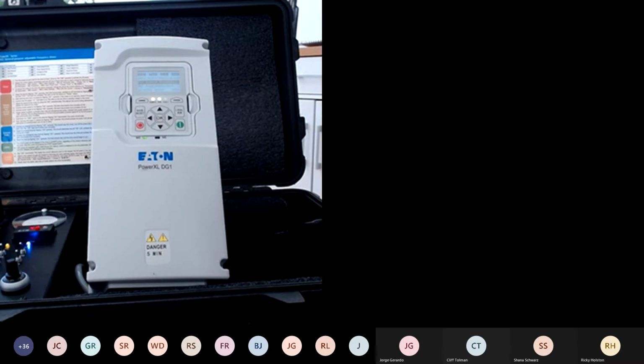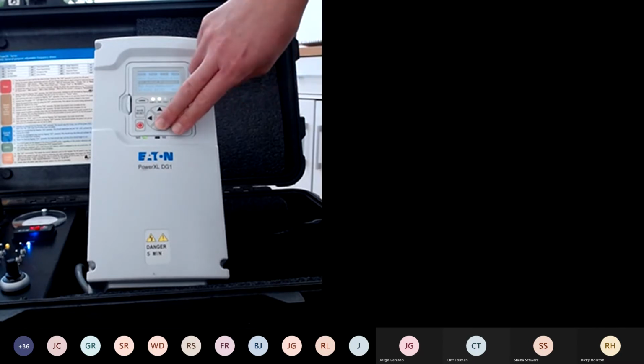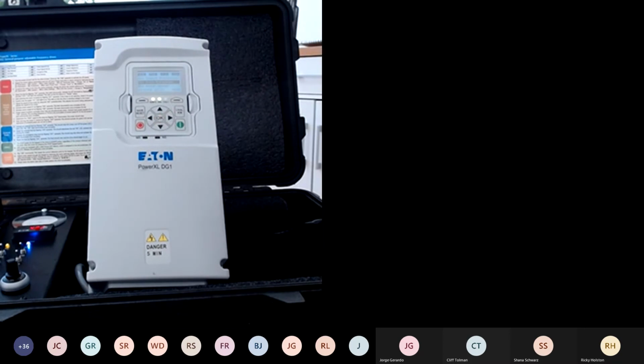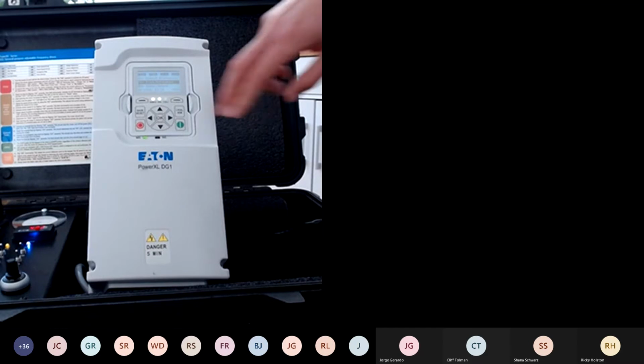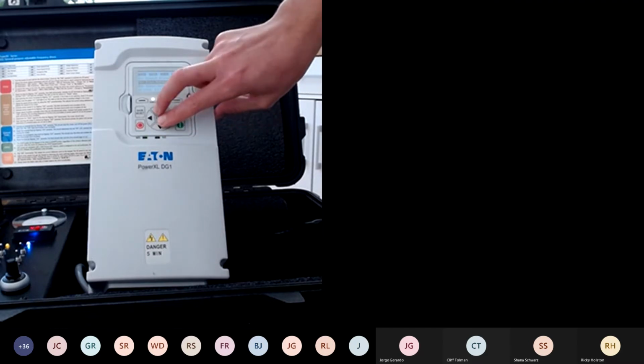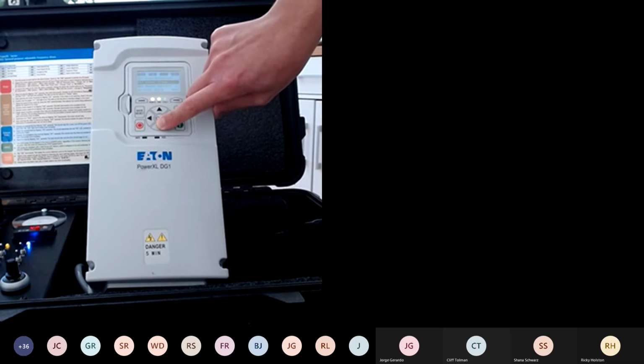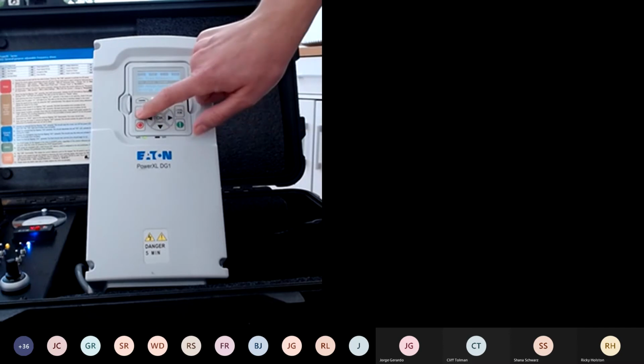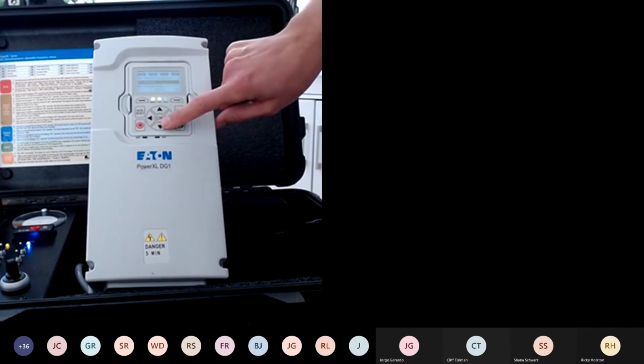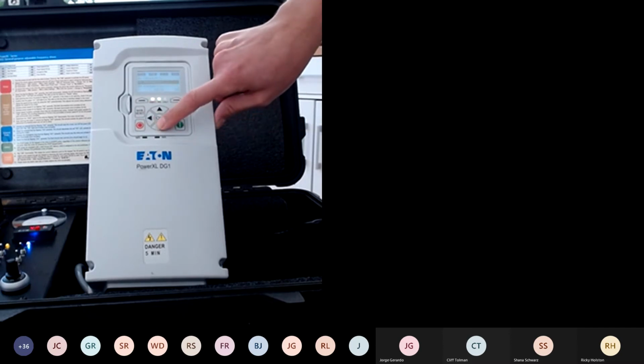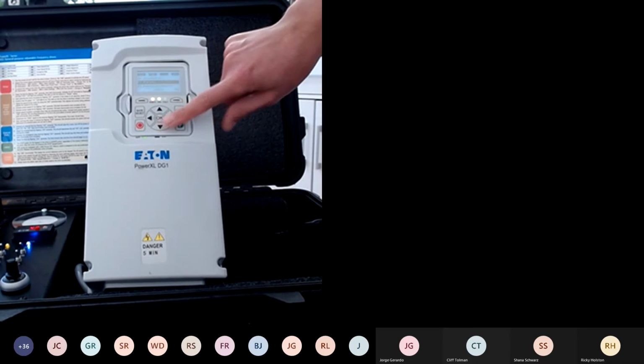They do have all these extra features on the drive itself. And all that monitoring can be either stored at the drive or downloaded if you have it connected directly onto your PLC control network. So again, these are the parameter menus. Let's go back here to the next menu on faults. So we have monitor here, we have parameters, and then we have faults.